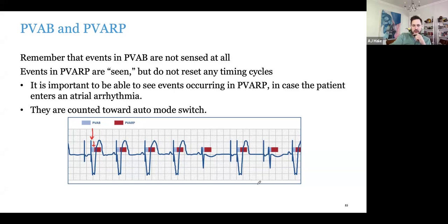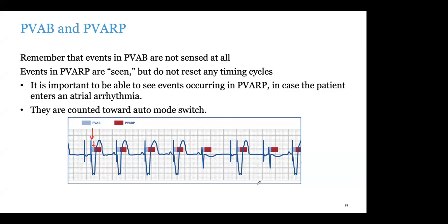Jared: On my implant, we actually had far-field R waves on the atrial channel. With the right programming and by changing the sensitivity, we can program around it. For implanters out there, be careful when implanting your RA lead that you're not putting those bipolar electrodes too close to the tricuspid valve — that's when you can pick up far-field R waves. If you can keep that RA lead a little bit higher where possible, you can usually limit the amount of oversensing on that atrial channel.